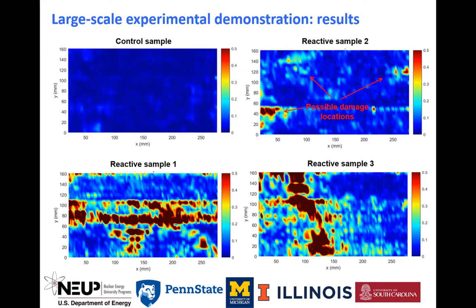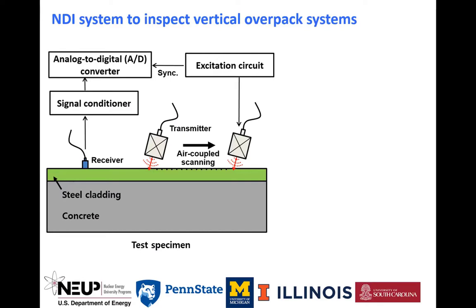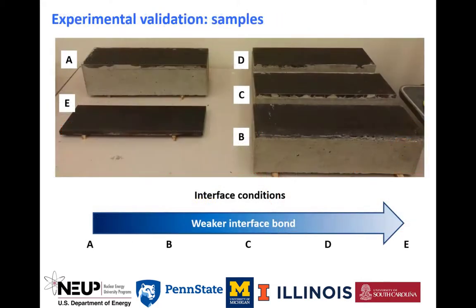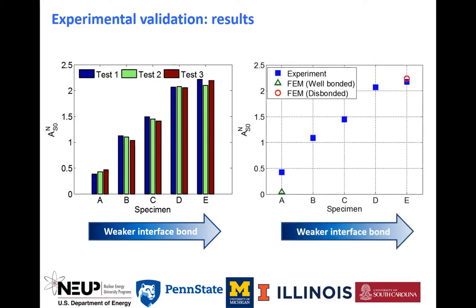The result from the control sample showed no indications of damage. In a separate effort, we developed an NDI system to inspect vertical overpack systems. The system is based on air-coupled scanning guided wave measurements, and the purpose is to quantitatively characterize the interface bonding condition between the steel clad and the underlying concrete layer. The NDI system was applied to lab-scale samples with various interface bonding conditions. Experimental results show that the interface bonding condition can be quantitatively characterized, the results are repeatable, and they showed good agreement with numerical simulation results.